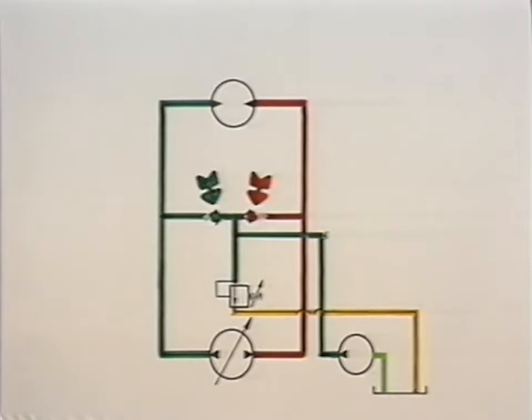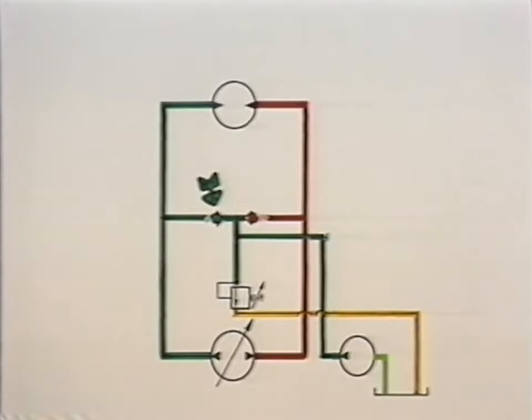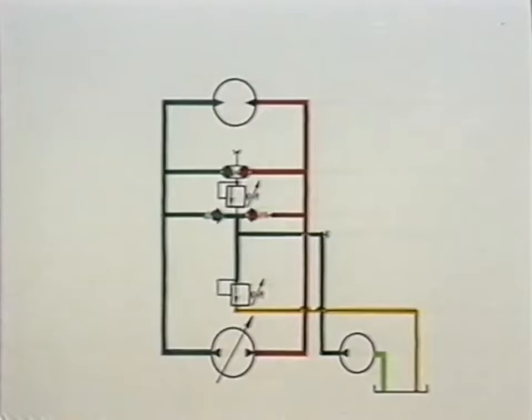These two check valves consequently serve to separate the high pressure side from the low pressure side and enable refill of the oil fed into the closed circuit, irrespective of which side is under high pressure.